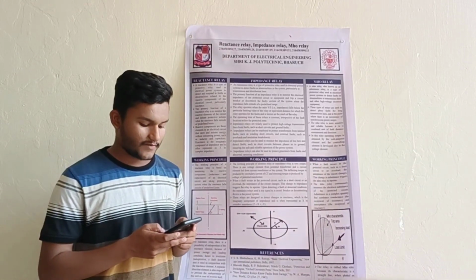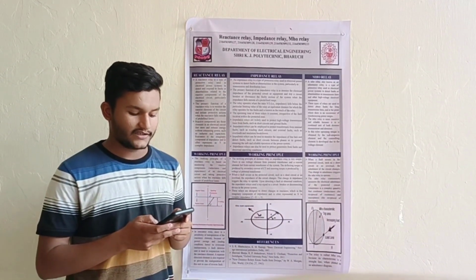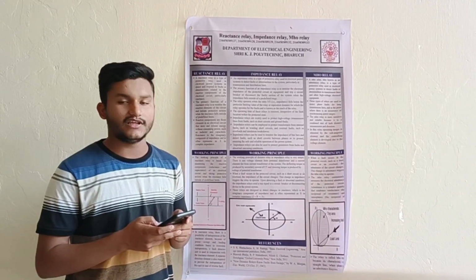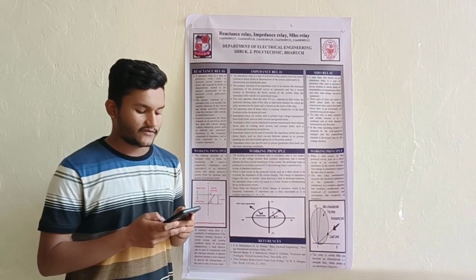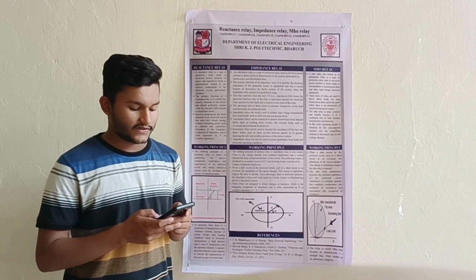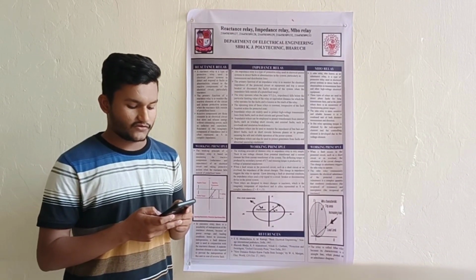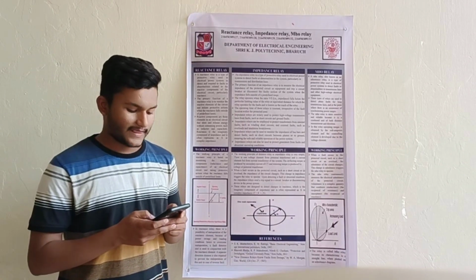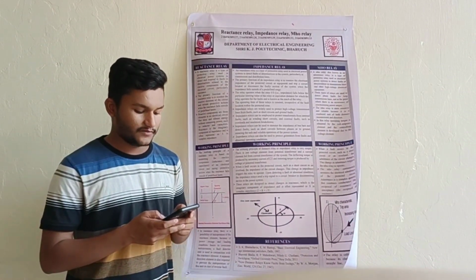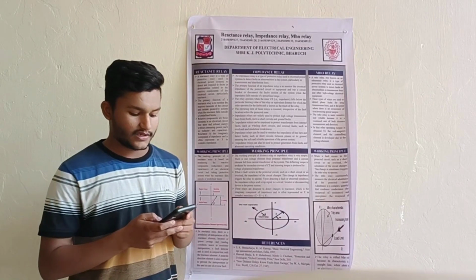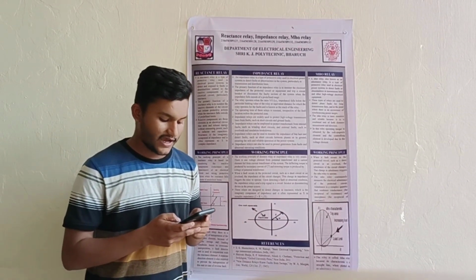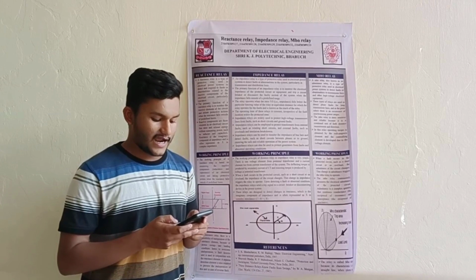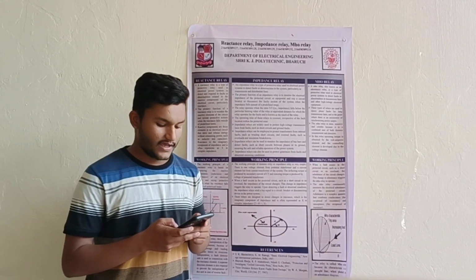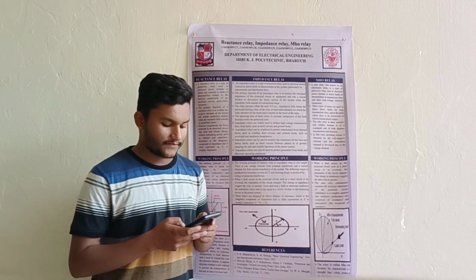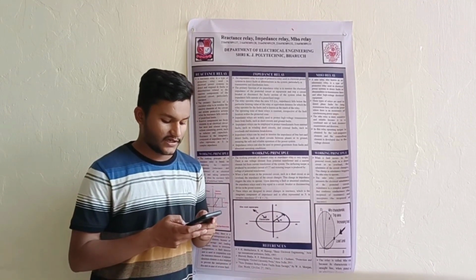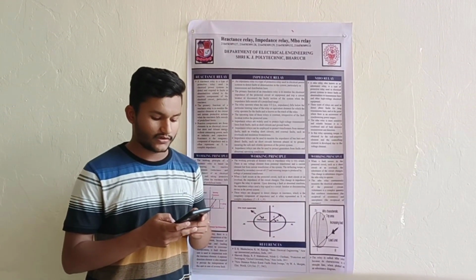Impedance relays are commonly used to protect transmission lines, generators, and transformers. They detect faults such as short circuits, ground faults, or phase-to-phase faults by quickly isolating the fault. Impedance relays help prevent damage to equipment and minimize downtime in the power system. There are different types of impedance relay, including Mho relays and circular relays.